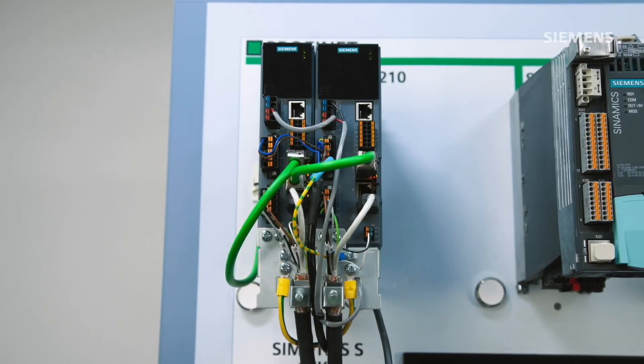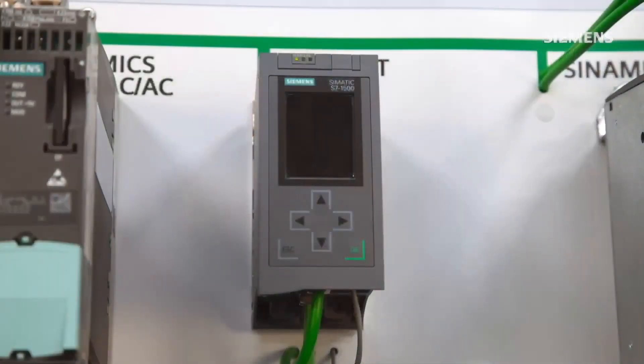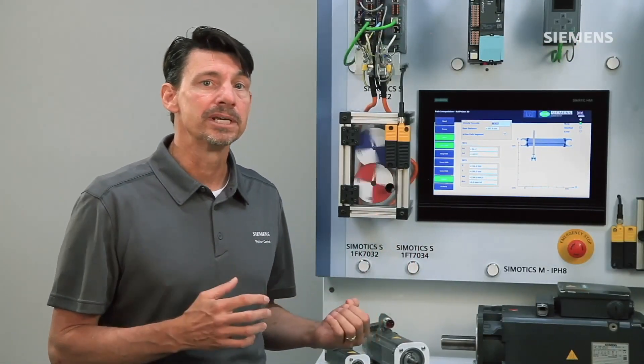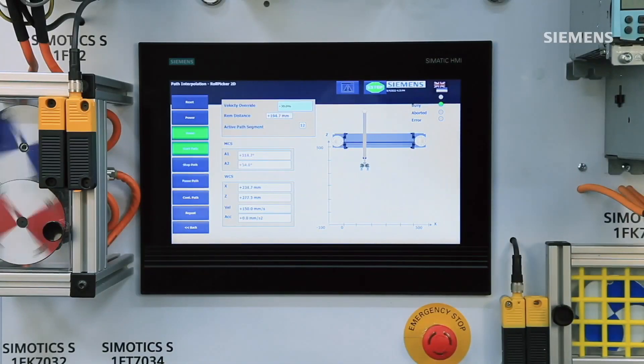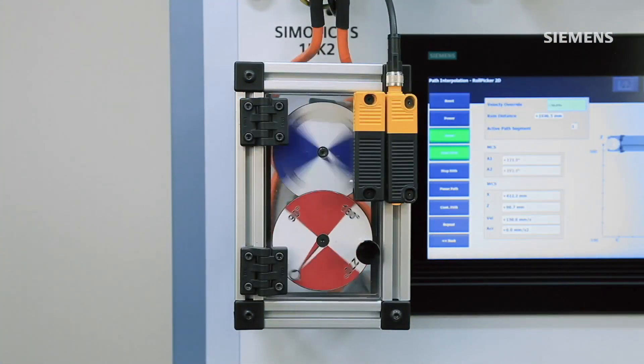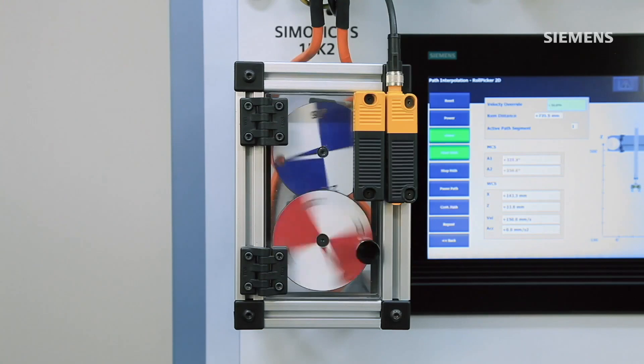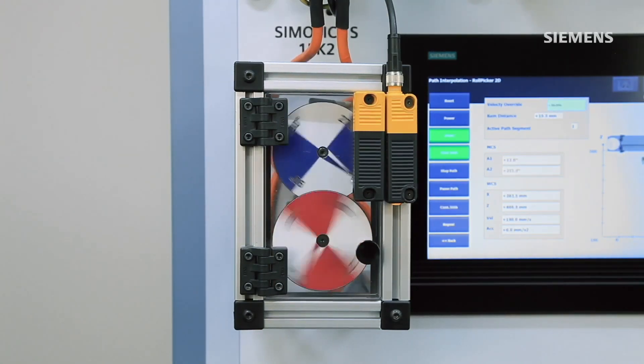Sinamics S210 servo system is the mid-range servo package at 7 kW, designed to offer an economic and dynamic servo functionality with the Simatic S7-1500T controllers. Ease of use starts with paired motors and utilizes a one-cable connection. The S210 drive automatically reads the motor nameplate and offers one-click tuning for straightforward startup. The technology objects in the S7-1500T are used to easily control motion in the S210 drive via PROFINET and safety via PROFIsafe.